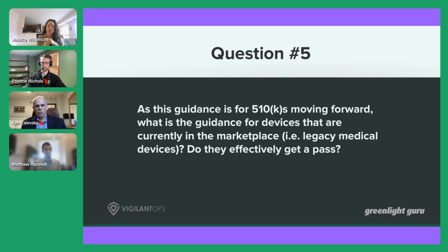But as Matt said, the post-market guidance also comes into consideration here, right? If there is a vulnerability or some kind of incident with a device that was pre-524B, we expect and will work with the medical device manufacturers to appropriately manage that risk. It doesn't matter that the device was cleared prior to 524B. And so we do want everybody to understand that 524B is an incredibly important milestone within FDA's regulation of medical devices. It is not the only thing that matters. It was not the beginning of FDA's medical device cybersecurity program. It is not the only thing that influences it.